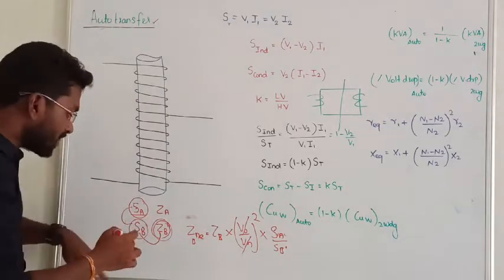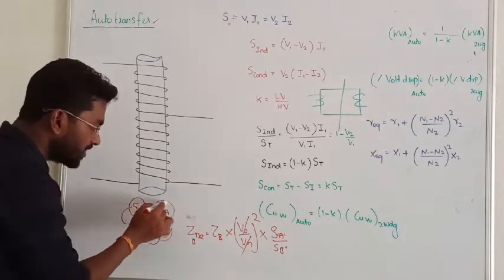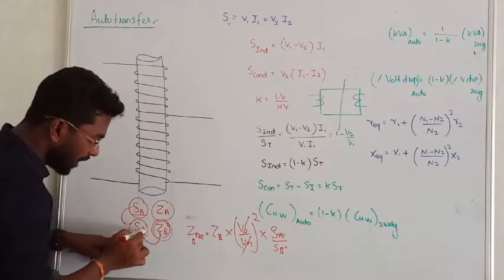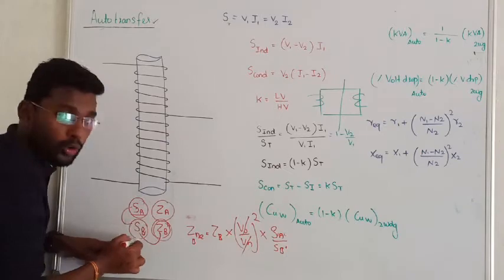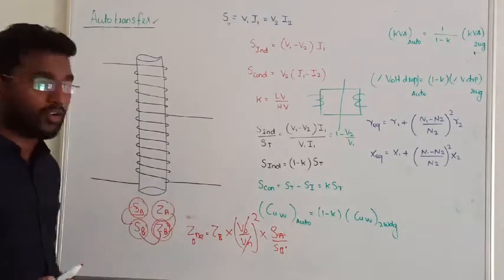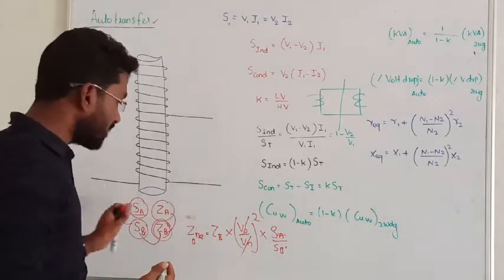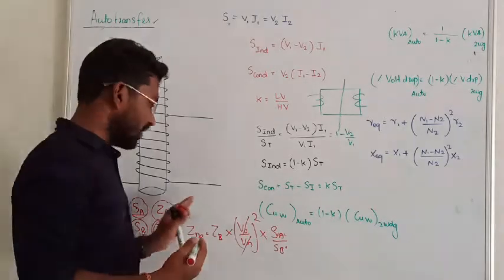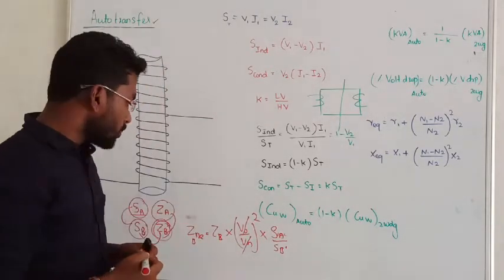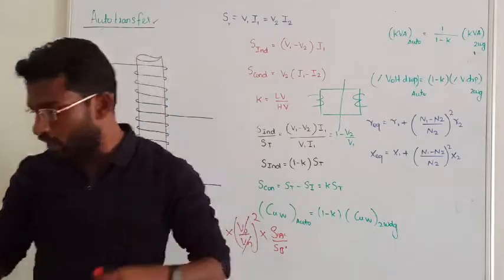This is how we transfer impedance from one rating to another. Suppose you choose ZB based on the kVA values of transformer A — you convert the impedance to the new kVA values corresponding to transformer B, and then you can perform the parallel operation. These are all the things we covered up to now.